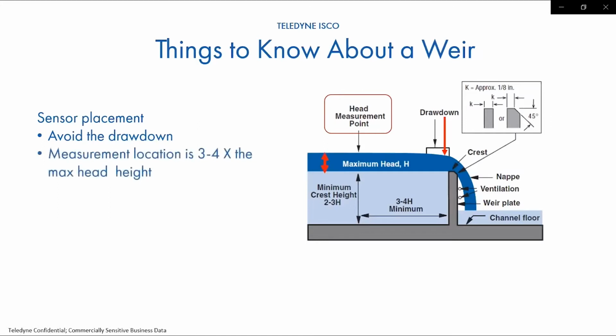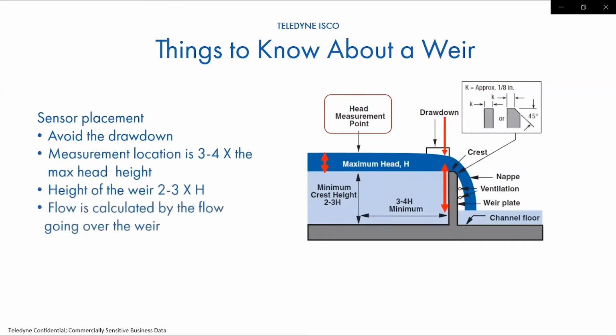And as I mentioned, you want to make sure your level measuring point is 3 to 4 times the maximum water head height back from the wall. And your height of the weir should be 2 to 3 times the height of the expected head height going over the top of the weir. And remember, the flow rate is calculated by the water going over the weir, so not the overall depth. So in this case here, if we had 1 foot of water over the top of the weir, and the weir wall was 3 feet, I'd have a total of 4 feet of water, subtract the 3 feet of dead space from the weir wall, and your head height would actually be 1 foot. And another important note is that you should have at least 20 times straight run in front of the flume, or the weir, to make sure you have smooth laminar flow coming through there.